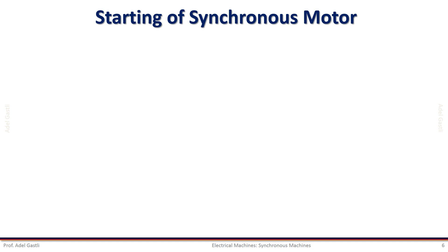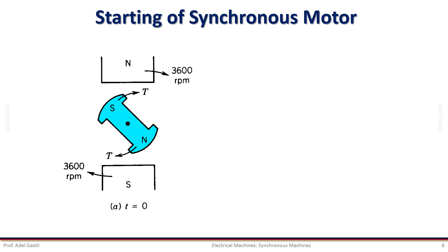Now we'll see why a synchronous motor has a problem during starting — in other words why the three-phase synchronous motor has zero starting torque. If the rotor field poles are excited by the field current and the stator terminals are connected to AC supply, the motor will not start; instead it will vibrate. The stator field is rotating so fast that the rotor poles cannot catch up or lock onto it because of the high inertia of the rotor which starts very slowly. For instance, if the stator flux is rotating at 3000 rpm clockwise and the rotor is initially at standstill, at one time T0 the dipoles on the rotor will have opposite polarities and will tend to attract each other. This creates a torque that will push the rotor rotation clockwise.